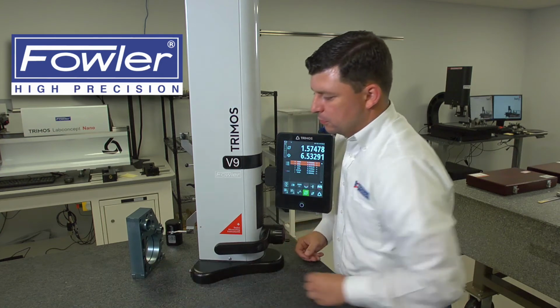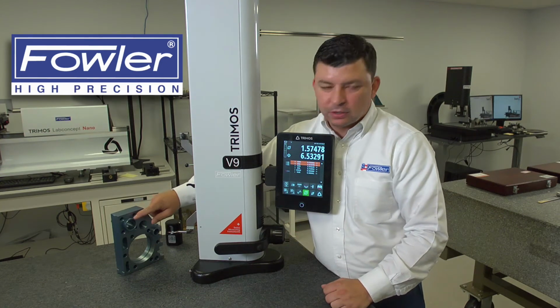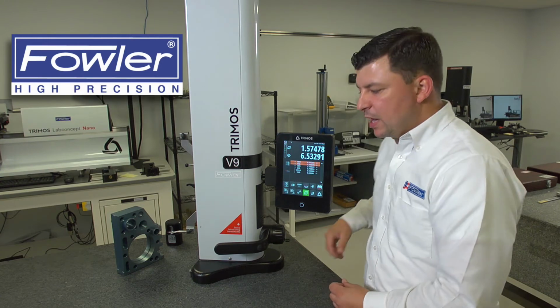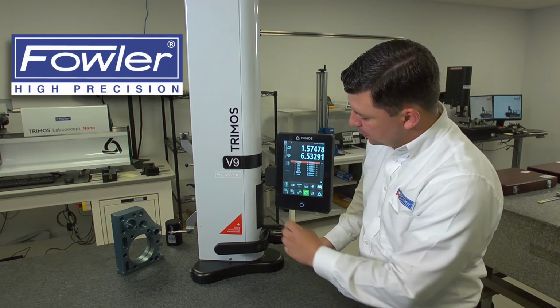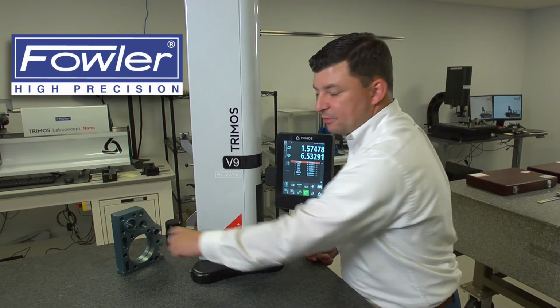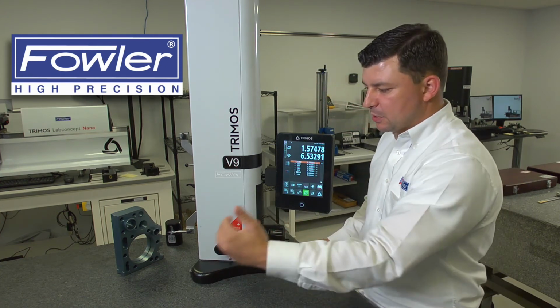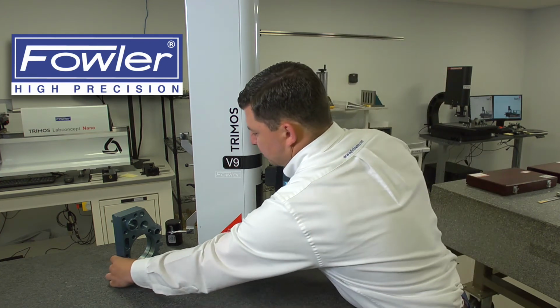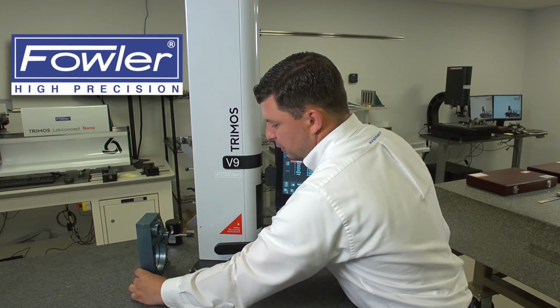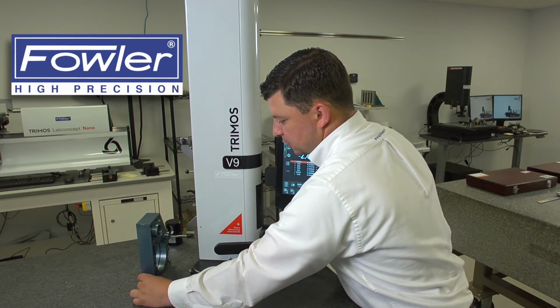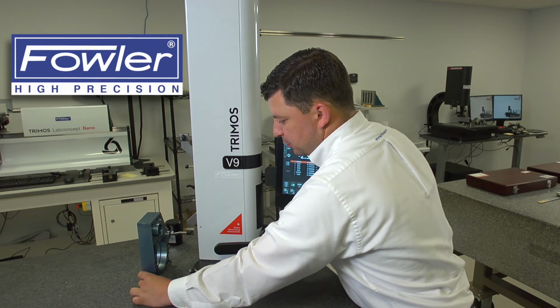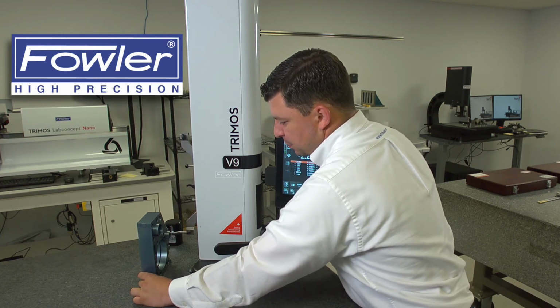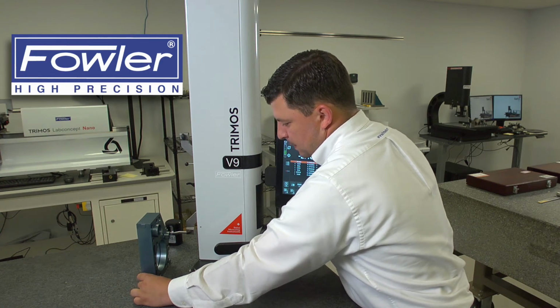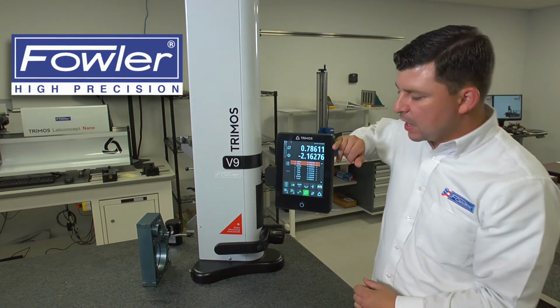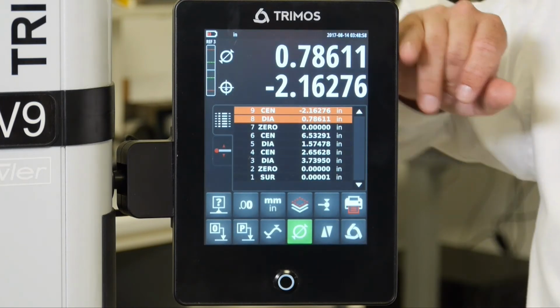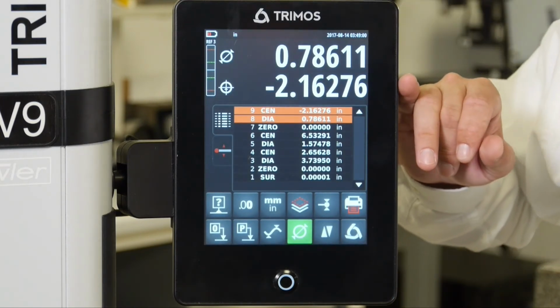If I want to know the distance from the center of one hole to the center of another hole, all I have to do is tap the 0 button to establish a 0 to whatever the last diameter that was measured, and then I can measure the distance to another hole. So if I proceed to this smaller diameter, if I engage the probe again, sweep through the bottom, drive up through the top, and sweep it back, if I release the probe, I have a diameter, an ID, and I also have a center-to-center distance.